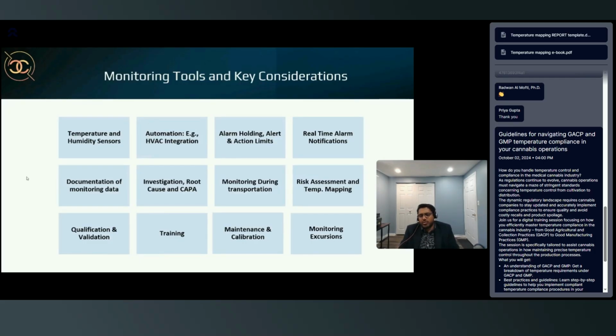I have a couple more slides to cover, so I'm just going to touch base on the last thing, which is monitoring excursions. Excursions are fluctuations in your temperature or humidity monitoring, which could happen because of multiple factors, and they do not represent an actual out of specification. It's like a spike: it goes up, it goes down, and it happens very quickly. If you have a spike for 2 hours, that's not an excursion, that's actually an out of specification. But if you have a spike which comes back within 15 to 20 seconds, or maybe half a minute to 1 minute, or maybe 10 minutes, that could be an excursion.